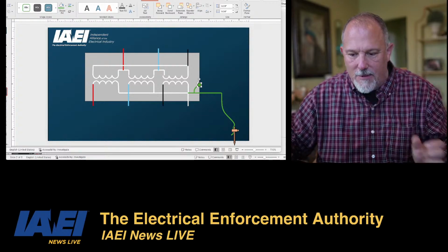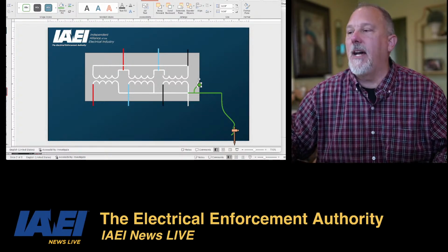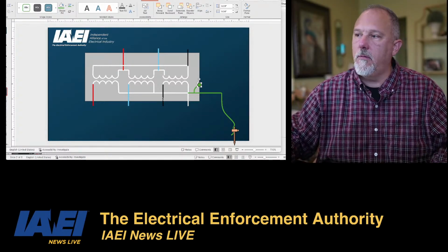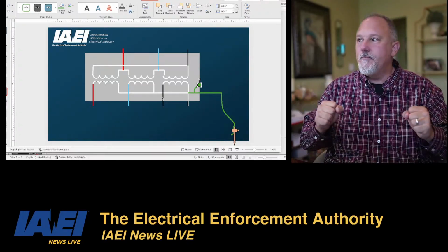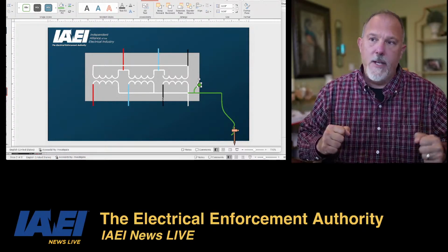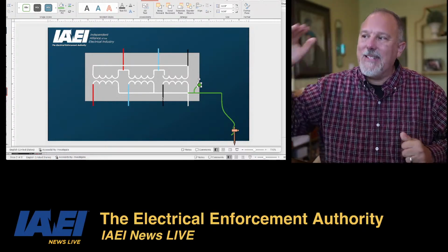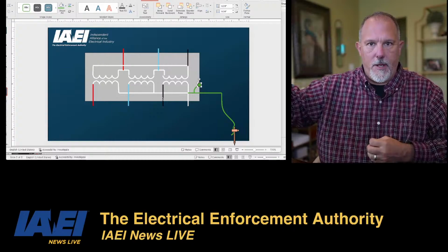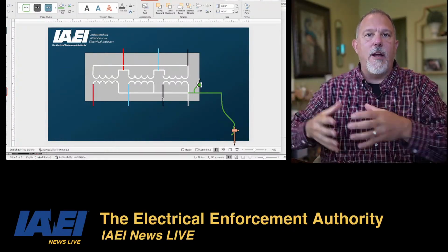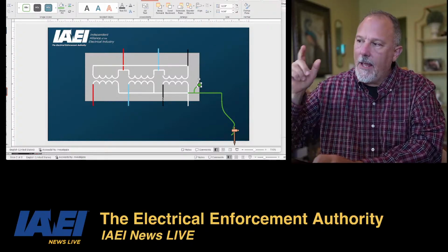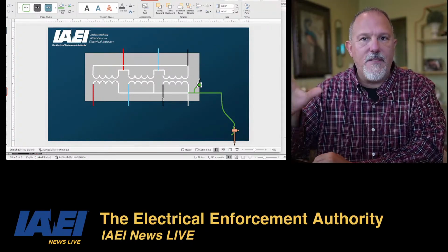Is it a grounded or ungrounded delta? Oh man, I'm glad you said that, Yummy Fudge. Because I have a delta primary, that doesn't mean my system is not grounded. It's a separately derived system.